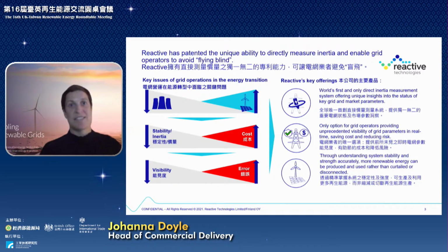This is because they rely on models of their network to estimate inertia, and those models are being undermined by fundamental changes in the network. For example, as more assets connect to the distribution network or behind the meter, it's much more difficult for the system operator at the transmission level to see through to the distribution level and understand what's actually happening. So just as they need a better understanding of inertia, their visibility is decreasing, driving error into their models and making decision-making more difficult.